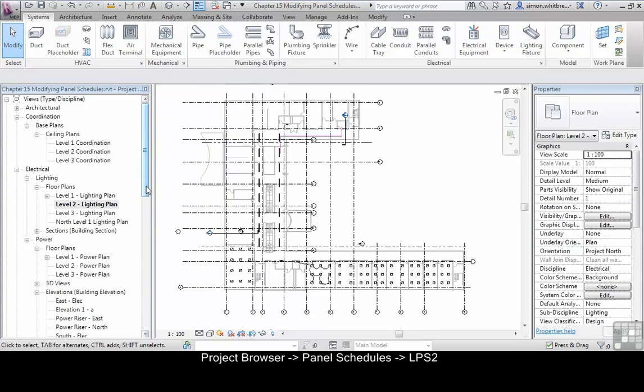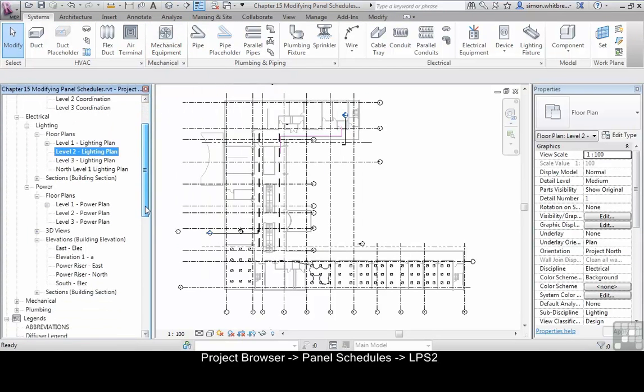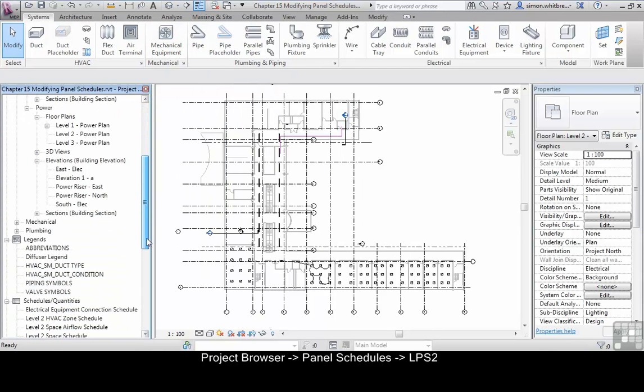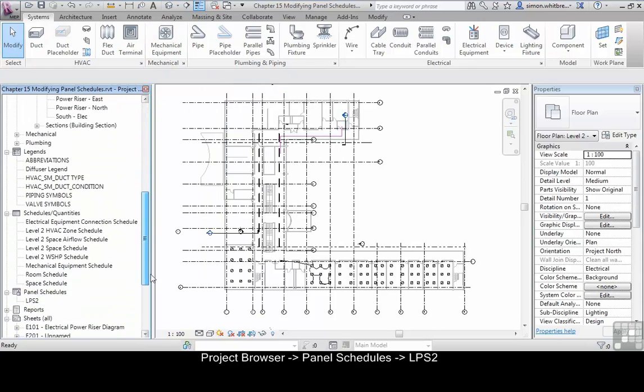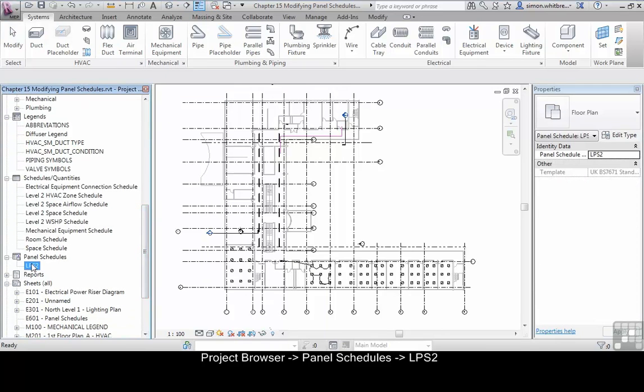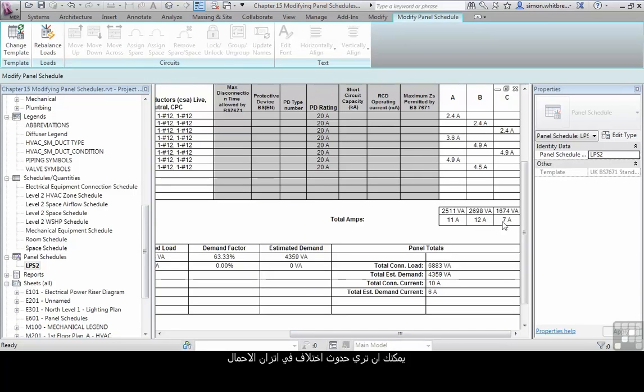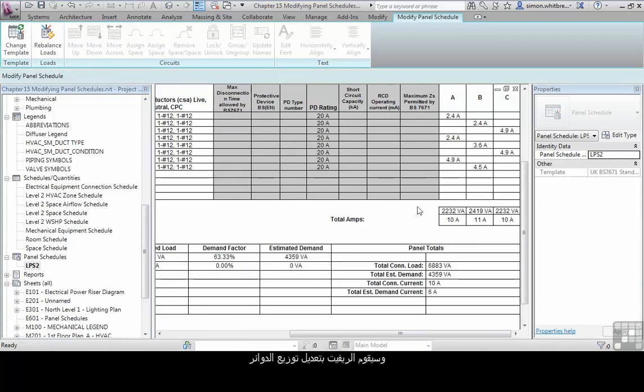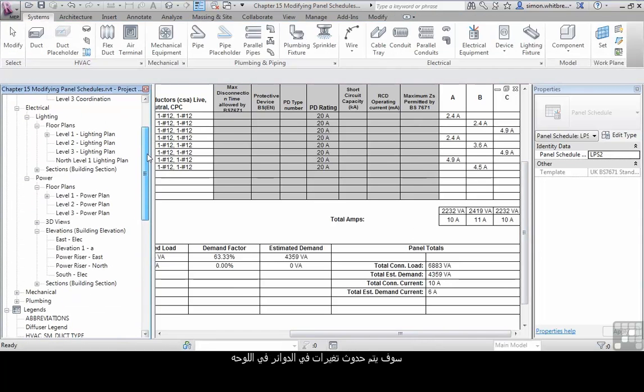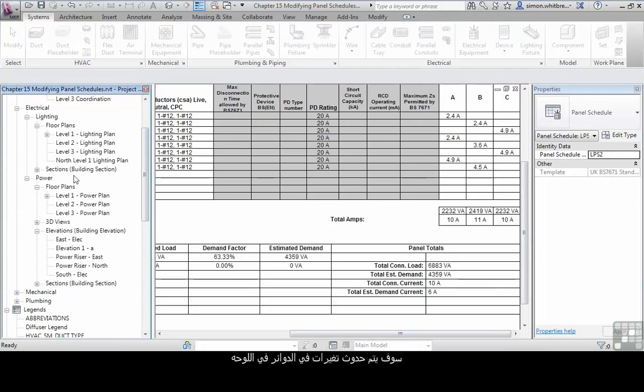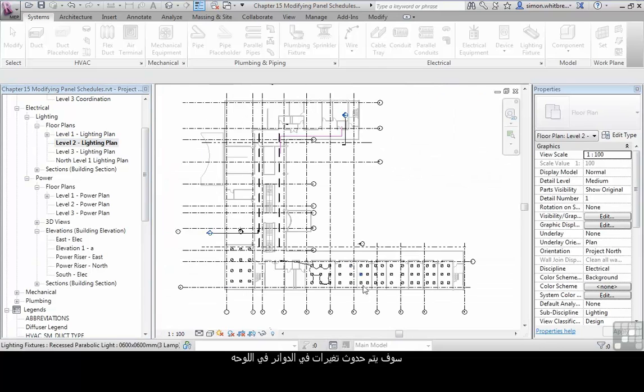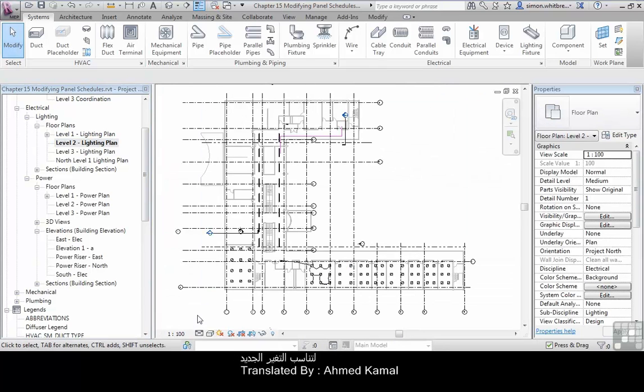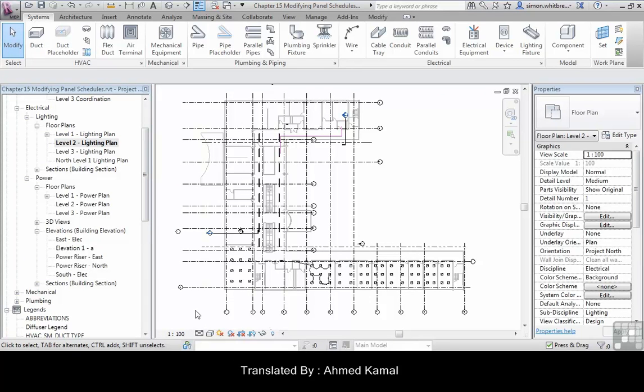Now if we scroll down in the project browser back to our panel schedule, you will see that our loads are a little bit unbalanced. We can click on rebalance loads and Revit will move the circuits around so that we do have balanced loads. The circuit references back in our plan will have changed to match the new balance.